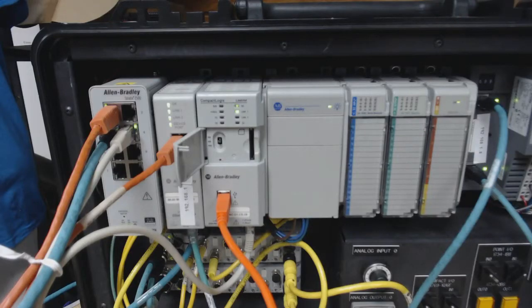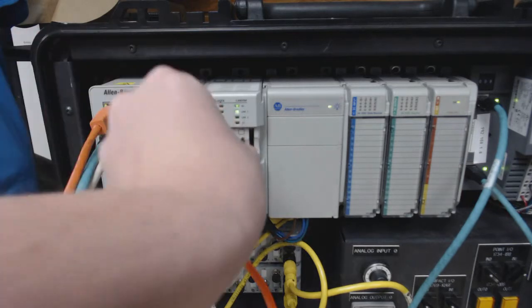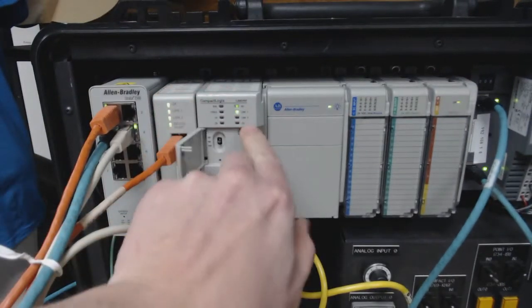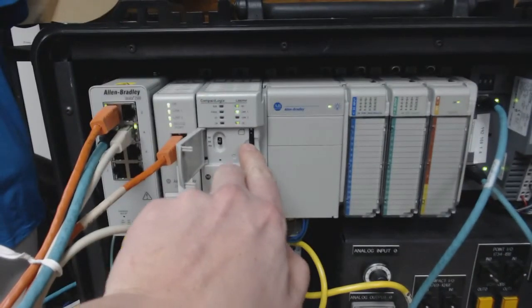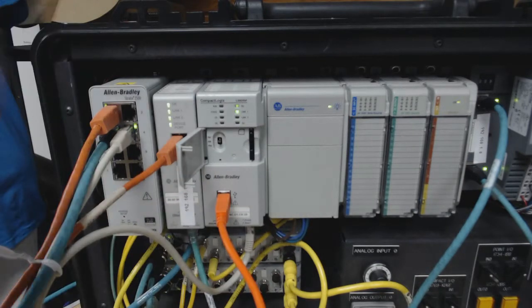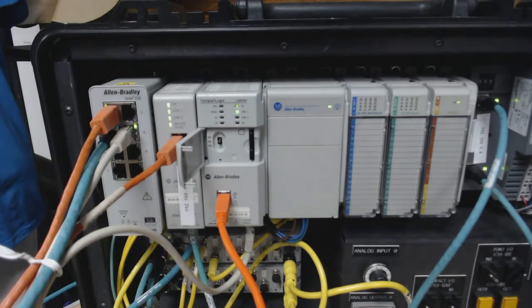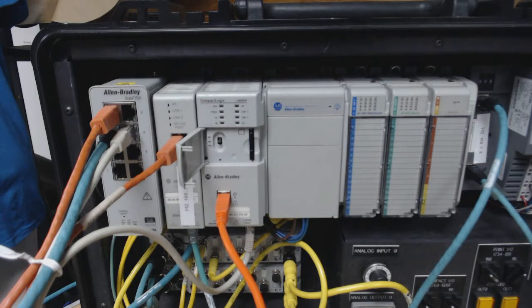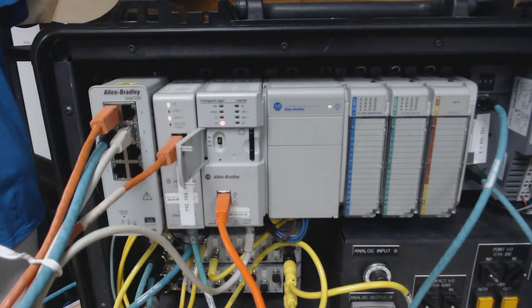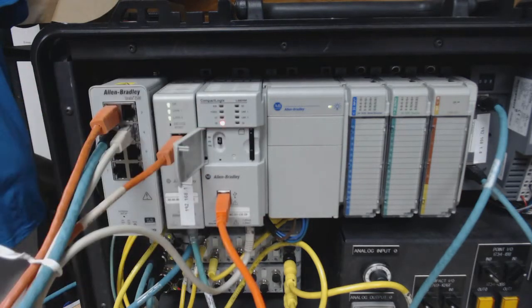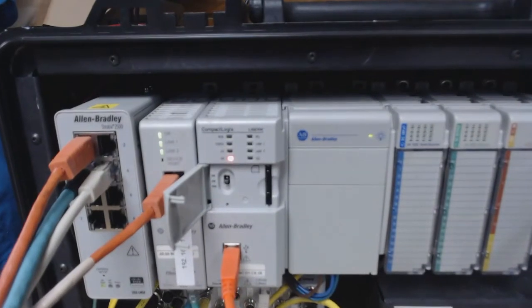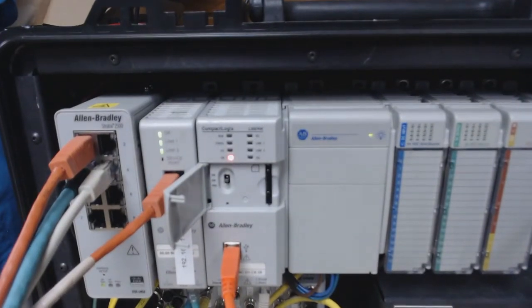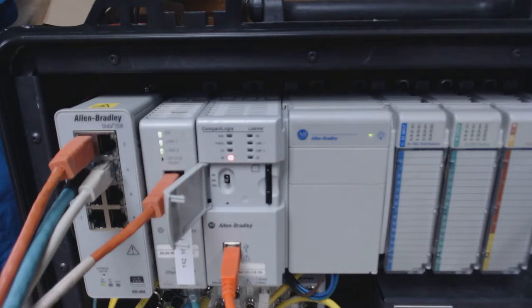So what I'm going to do here is just go ahead and put our SD card back into the processor until that clicks. And then I'm just going to cycle power. And I just wanted to show you what happens when I do that. Let me turn the power back on. You'll see the SD light down here on the CompactLogix start to flash a few times. See if you guys can see that once it comes on. And that just, you know, that's the processor reading from the SD card, indicating that it is going to go ahead and load from there.